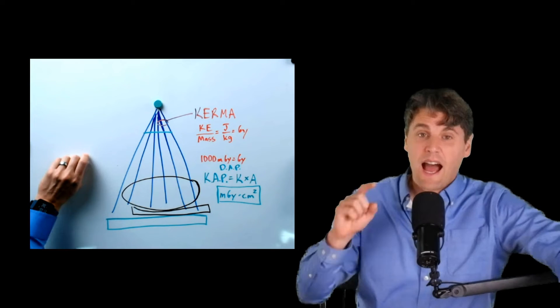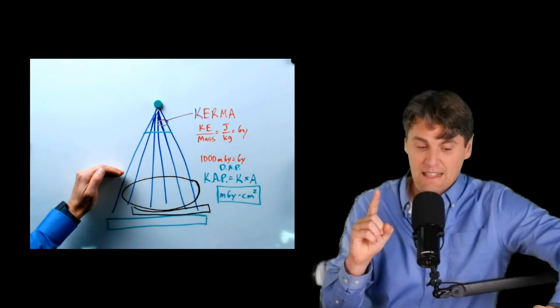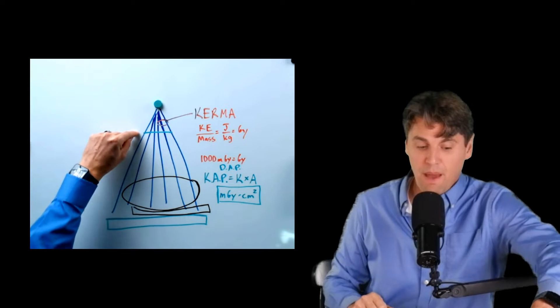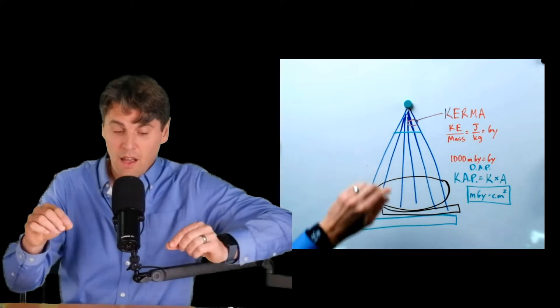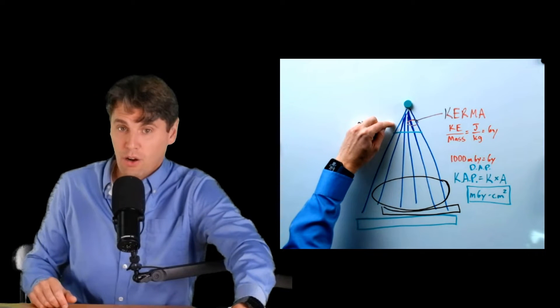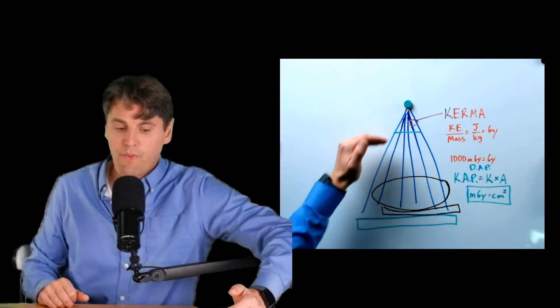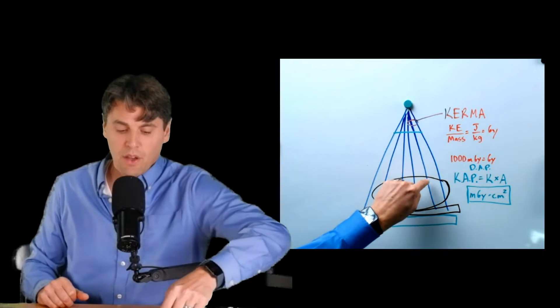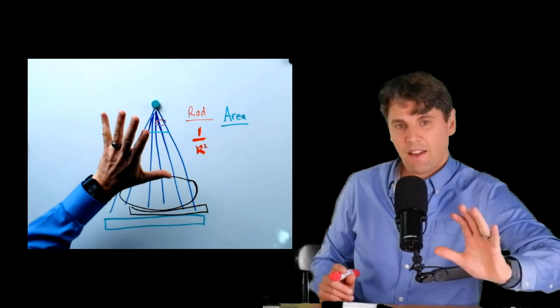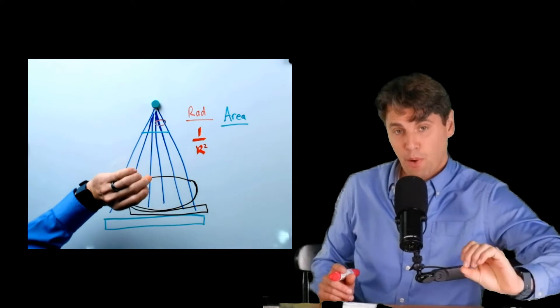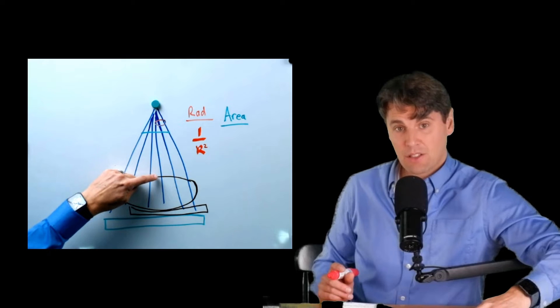Then an important question is how does the Kerma area product change as a function of the distance from the x-ray tube? We're often going to be measuring the Kerma area product very close to the x-ray tube. We have the distance measurement there, and then we also have our Kerma measurement there with an ion chamber, for instance. And then how does that actually change as you move further away from the x-ray tube? Because we're actually concerned about the irradiation of our patient, which is way down here. If you remember from our exposure factors video, the exposure actually goes like 1 over R squared, where R is the distance from the x-ray tube.